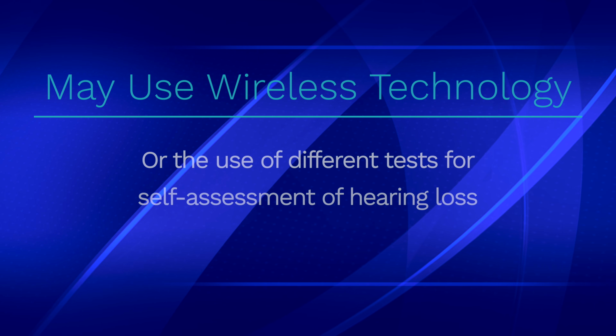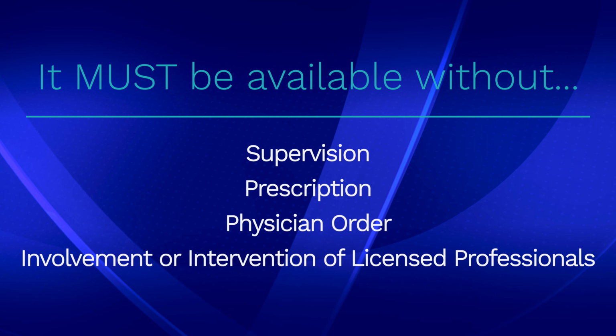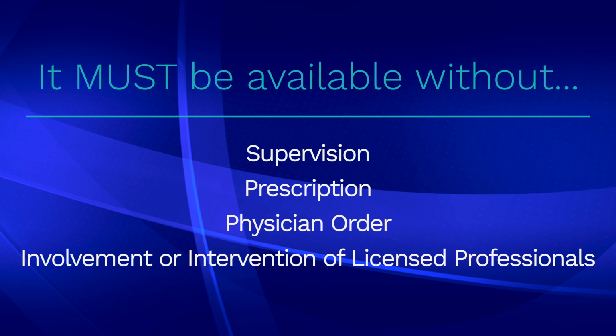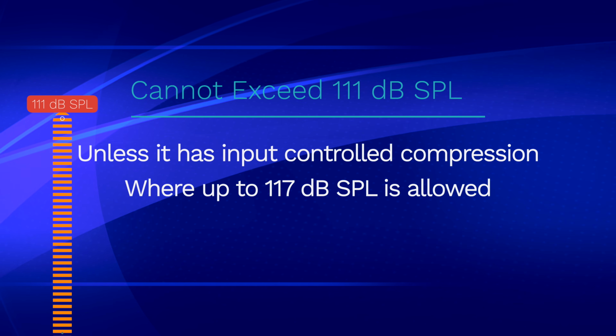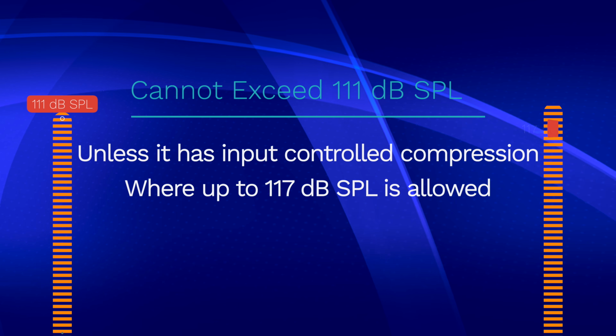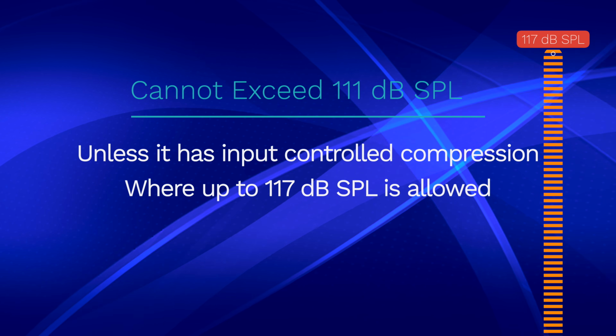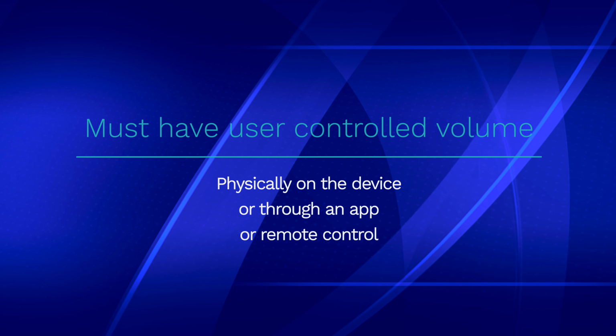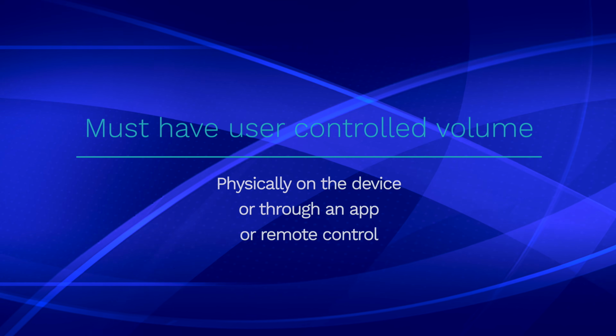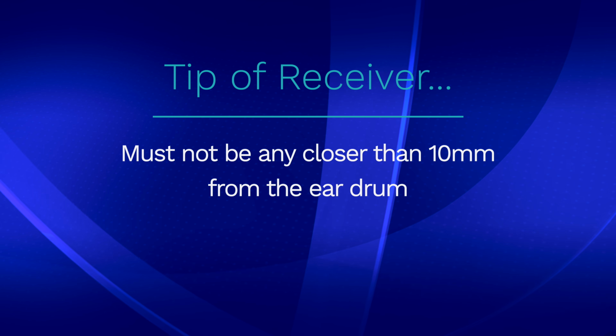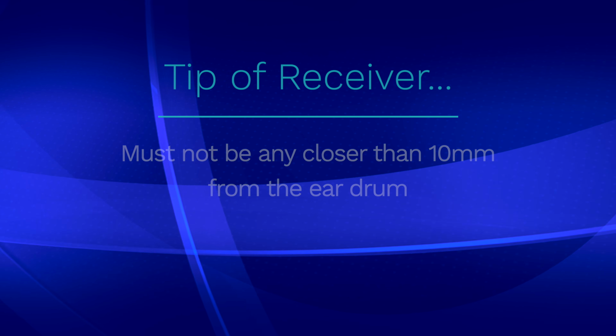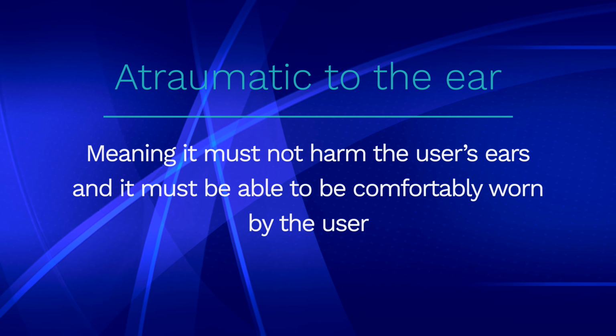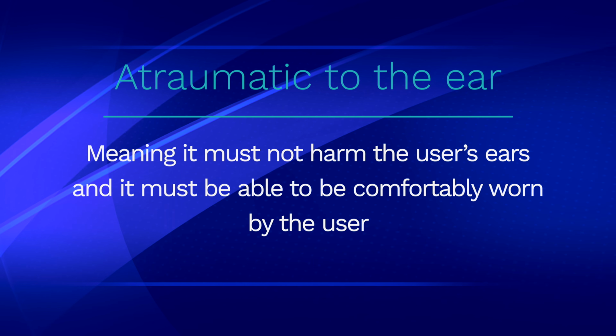It may use wireless technology or the use of different tests or self-assessment of hearing loss. It must be made available without supervision, without prescription, without a physician order, and without involvement or intervention of a licensed individual. OTC hearing aids cannot exceed a maximum output of 111 dB SPL at any frequency unless it has input-controlled compression, in which case it shall not exceed 117 dB SPL at any frequency. It must have a user-controlled volume either physically on the device or through an app or remote control. The tip of the receiver must not be any closer than 10 millimeters from the eardrum. It must be atraumatic to the ear, meaning it must not harm the user's ears, and it must be able to be comfortably worn by the user.